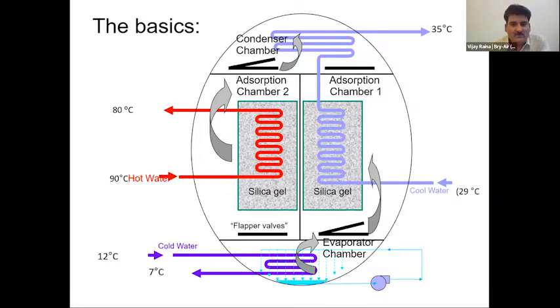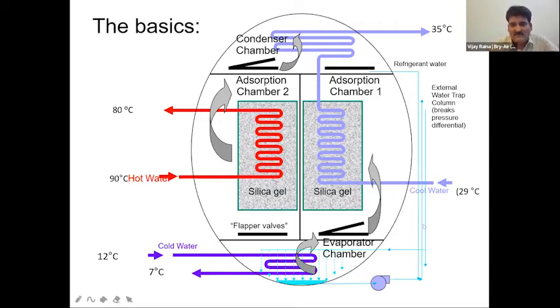And in addition to the chilled water heat load, we are giving heat load as hot water. So there are 2 heat loads on the cooling tower. So heat load dissipation is more in our adsorption chiller as compared to conventional chillers. So when refrigerant water is reaching the condenser, we need the same refrigerant. So you see only 2 flapper valves are on. So refrigerant is moving like this in adsorption chamber 1. At the same time, refrigerant which was earlier adsorbed by chamber 2 is released and reaches the condenser chamber. The same refrigerant water is now used in the evaporation chamber. So it comes with gravity flow, and we circulate the refrigerant in the entire evaporation chamber.